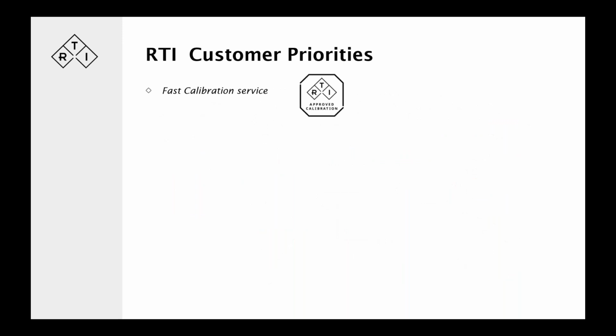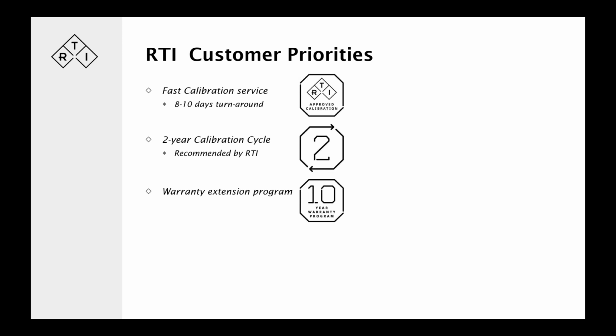So what we offer, which is also a useful tool, is a supplier that provides, for instance, a fast calibration service, where we today have a turnaround time of about 8 to 10 days when it comes to calibration. Our recommended calibration cycle is 2 years. That's what we find is a decent time. Of course, it's up to the customer to determine the calibration cycle, how often they need to calibrate their equipment. But our recommendation as a manufacturer is once every 2 years. There's a warranty extension program as well, where if you maintain the 2-year calibration cycle, you can extend the warranty up to about 10 years.